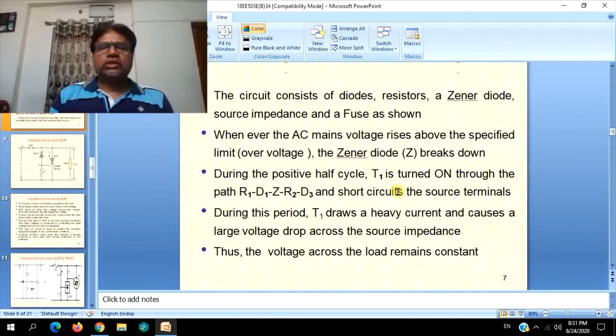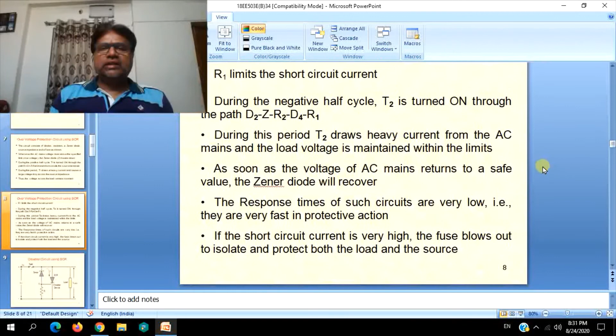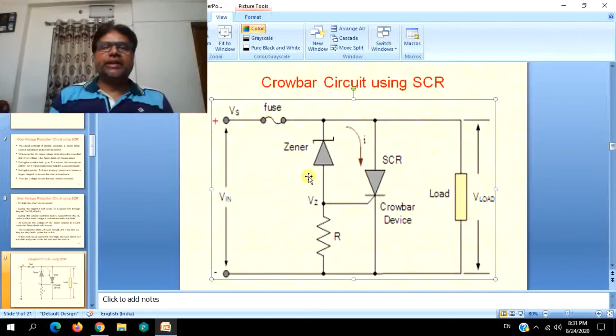There are no other current limiting resistors, as shown in the case of overvoltage protection circuits like the current limiting resistor R1. It results in a dead short circuit applied across the source terminal. So what happens? Very high current flows. Due to that, the fuse will be blown out, open circuiting the circuit, and the load will be disconnected from the source. Thus both source and load will be isolated. So crowbar circuits are used under abnormal conditions where very high energies are to be interrupted.